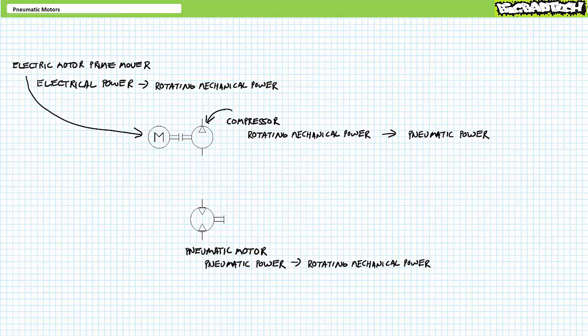Air motors are a great fit for flammable atmospheres or clean environments that might not be suitable for electric motors or dirty hydraulic motors. Additionally, air motors can stall at no risk of overheating or damage, as would a continually energized electrical motor in a locked rotor condition. Air motors can be found in numerous applications including industrial saws, drills, and grinders, and pneumatically powered handheld tools. Just remember to put your hearing protection on when you use them.